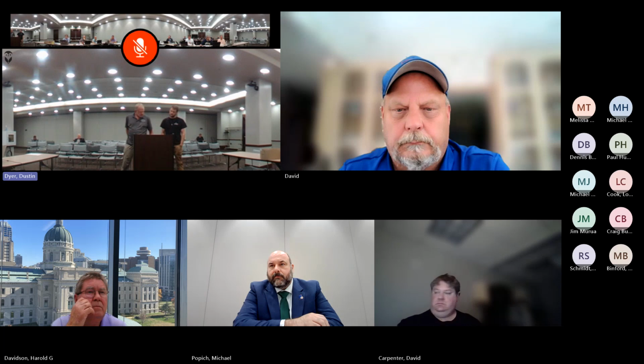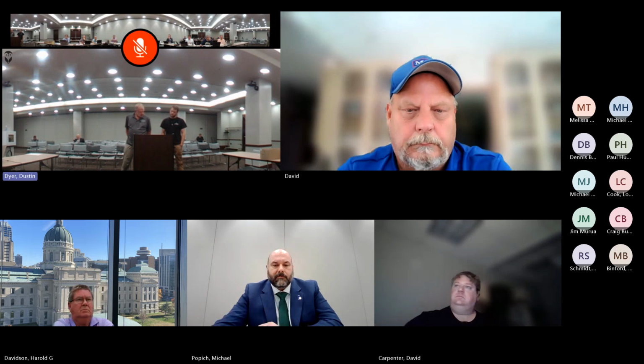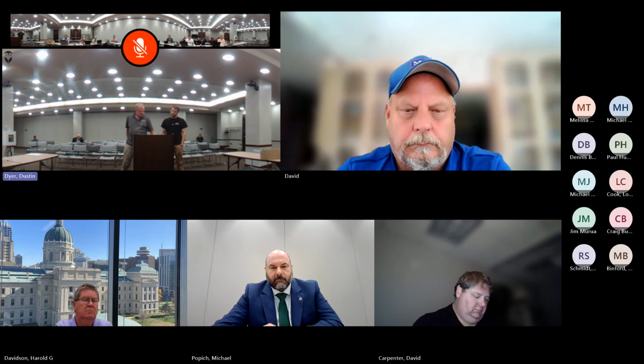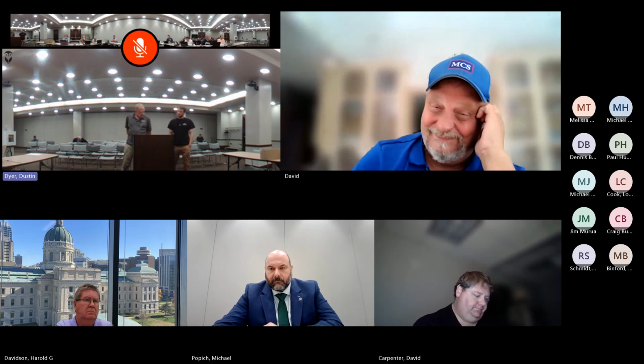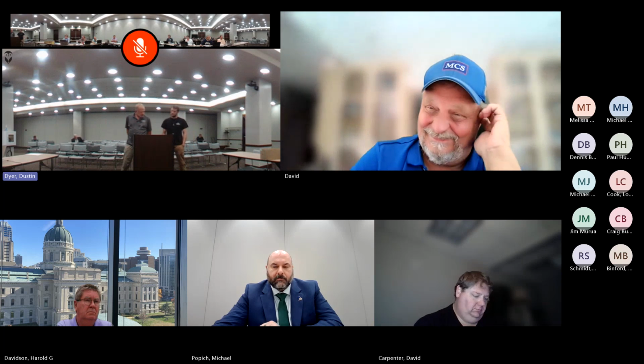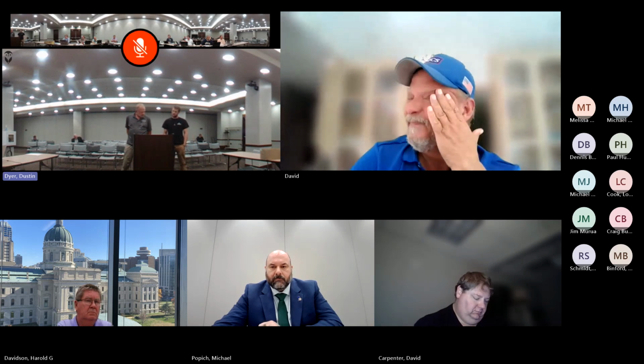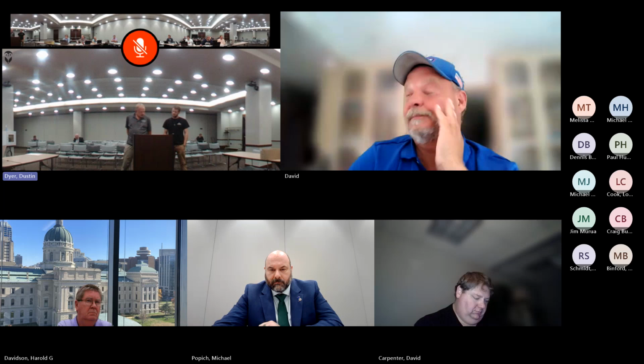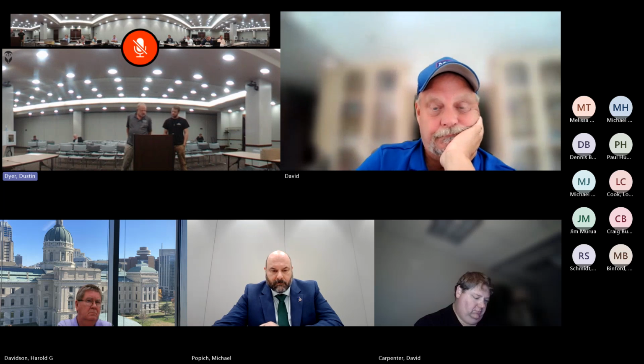Sprinklers shall not be omitted from any room merely because it is damp, of fire-resistive construction, or contains electrical equipment. Some of the exceptions are any room where the application of water or flame and water constitutes a serious life or fire hazard, or any room or space where sprinklers are considered undesirable because of the nature of the contents, when approved by the fire code official.